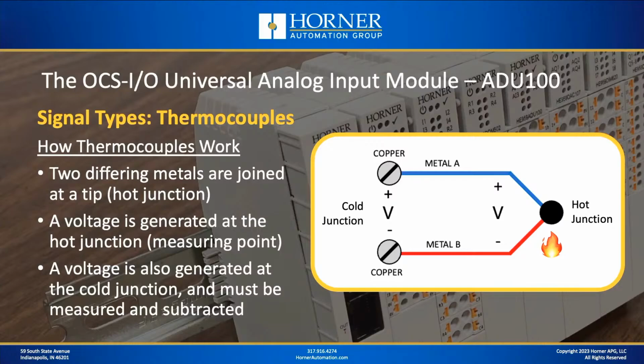Another factor that makes thermocouples tricky to deal with is that when you connect each lead of the thermocouple to your measuring instrument, the ADU100 in our case, a small voltage is also generated at those points, which is effectively error. So any quality thermocouple measuring instrument, like the ADU100, must measure the temperature at what's called the cold junction and calculate what that voltage loss is and compensate for it, so that the reading that's reported is strictly the temperature at the hot junction, or the tip of the probe. That's a couple of the factors that make thermocouples tricky to deal with.